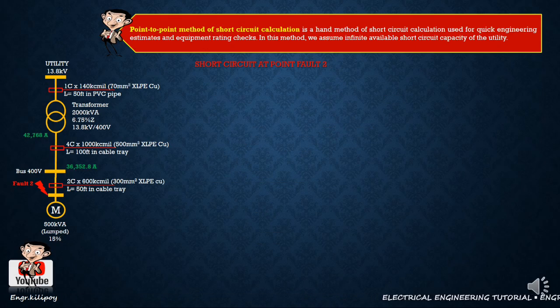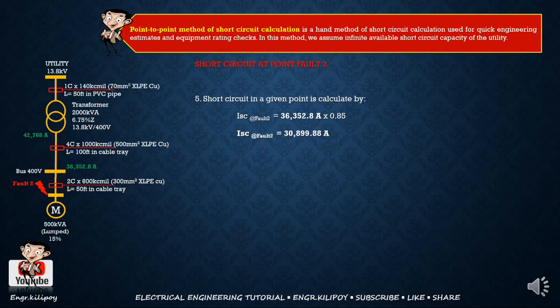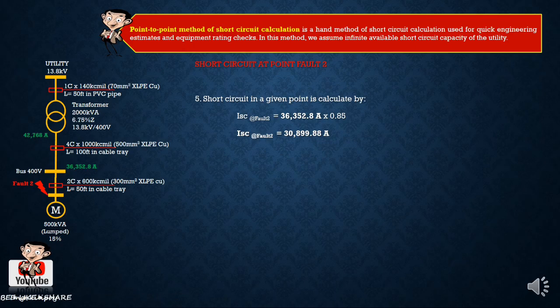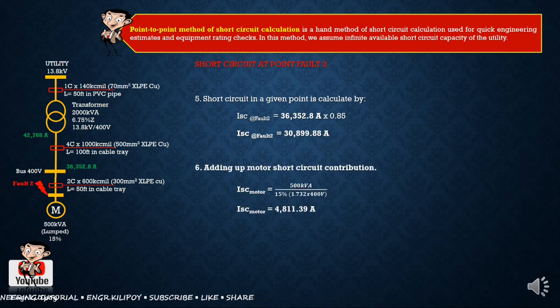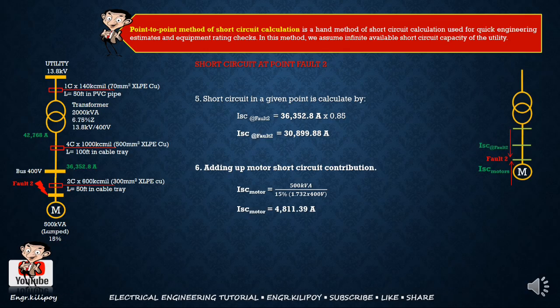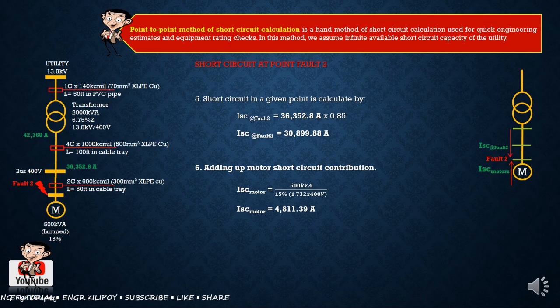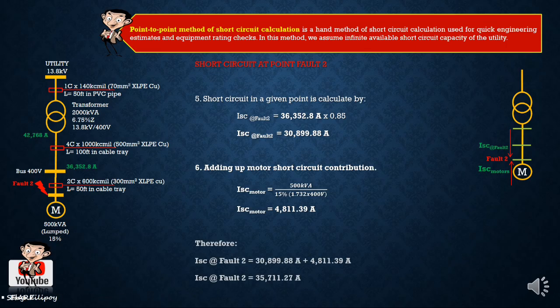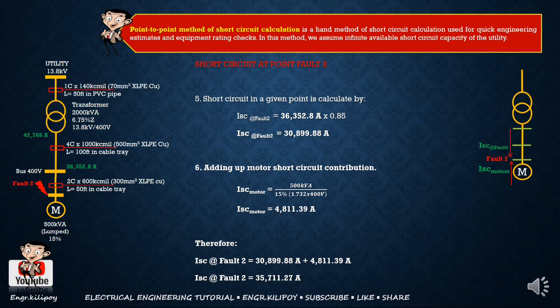So, at this point, may available na 36,352 ampere doon sa 400 volt bus now. So, mangyayari dyan, meron kang motor load contribution again na 4,800 ampere. Mangyayari dyan, yung fault na 36,352 pupunta sa fault point, which is the fault 2. At yung motor contribution mo, pupunta rin yan dyan sa short circuit point na fault 2. So, magkakaroon sila ng 35,711.27 ampere or 35.7 kiloampere.